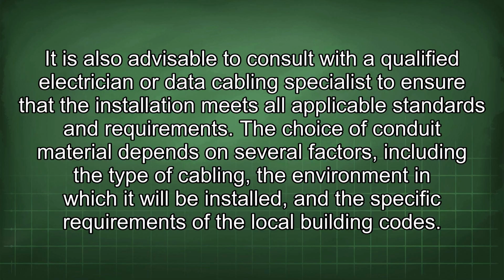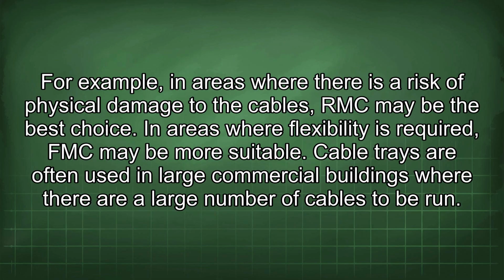The choice of conduit material depends on several factors, including the type of cabling, the environment in which it will be installed, and the specific requirements of the local building codes. For example, in areas where there is a risk of physical damage to the cables, RMC may be the best choice. In areas where flexibility is required, FMC may be more suitable. Cable trays are often used in large commercial buildings where there are a large number of cables to be run.